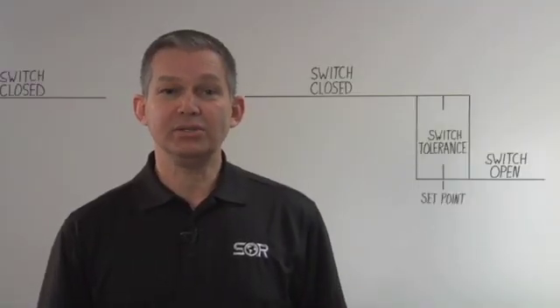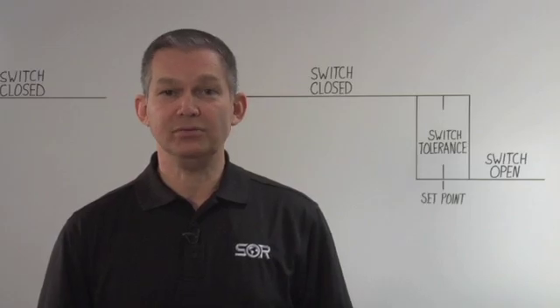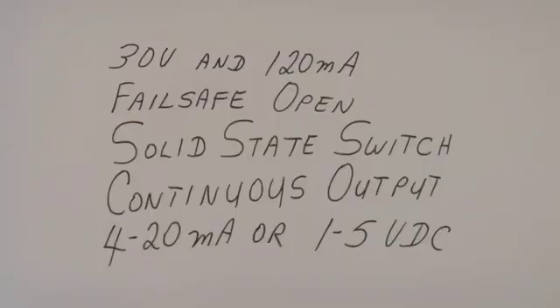So, let's summarize the principal features of the 805QS. It offers a configurable solid state switch that is rated to 30 volts and 120 milliamps with an accuracy of plus minus 2% of the upper range limit. In consideration of the set point tolerance, SOR recommends the use of latching logic in conjunction with the 805QS.